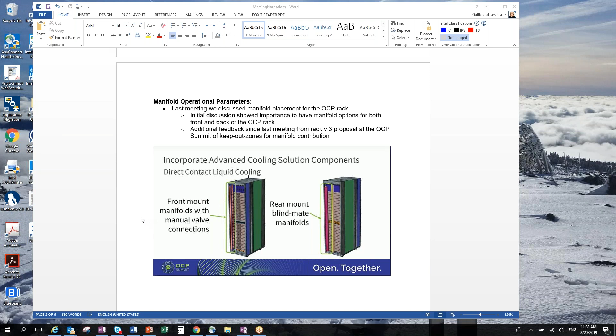With that, regarding the rack manifold operating parameters, I started putting some data together. This is really data found online, looking at different CDU suppliers and CDU options, and the three different CDU options we have: in-rack CDU, in-row CDU, and virtual CDU. So it's about creating the operational parameters the manifold may experience from the different CDU options possible for the installation.